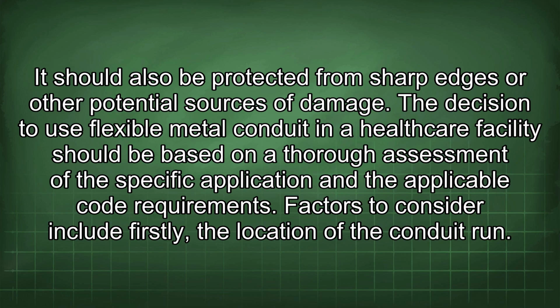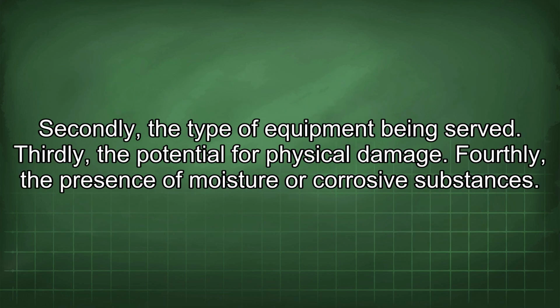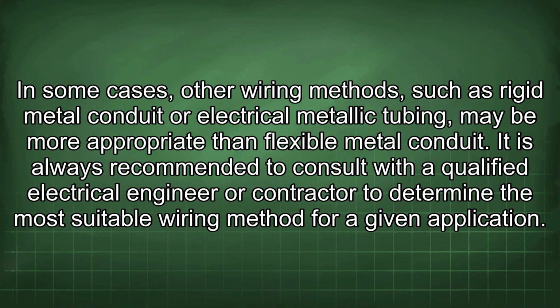The decision to use flexible metal conduit in a healthcare facility should be based on a thorough assessment of the specific application and the applicable code requirements. Factors to consider include, firstly, the location of the conduit run. Secondly, the type of equipment being served. Thirdly, the potential for physical damage. Fourthly, the presence of moisture or corrosive substances. In some cases, other wiring methods such as rigid metal conduit or electrical metallic tubing may be more appropriate than flexible metal conduit. It is always recommended to consult with a qualified electrical engineer or contractor to determine the most suitable wiring method for a given application.